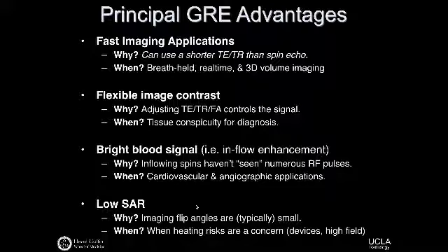The gradient echo sequence, however, uses a lot of RF pulses, but they're low in amplitude, at least low in amplitude. So this technique can be a low SAR technique, and we don't have to sometimes worry as much, if you will, about patient heating. And that might be really relevant when patients have implanted devices, or if the clinical field moves towards 7 Tesla imaging, 11 Tesla imaging. Turns out SAR is a bigger problem there.